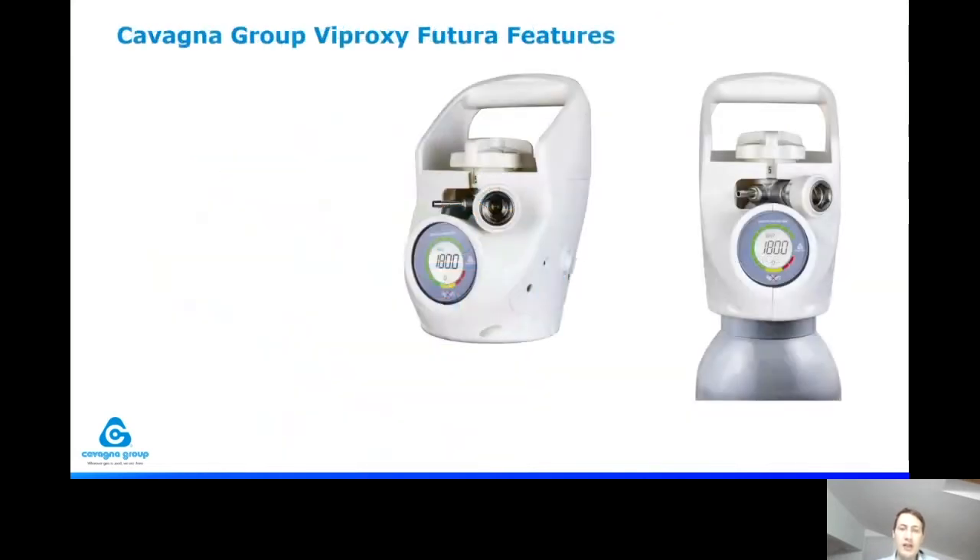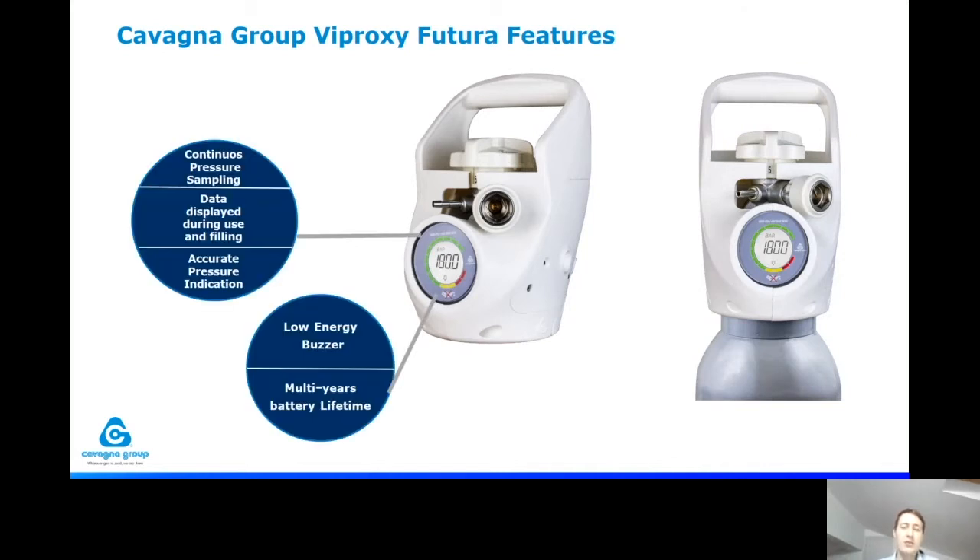The Viproxy Futura is the oxygen valve dedicated to the healthcare sector, for use in hospitals, ambulances, and home care. It has different features, including the ability to monitor and see from the display the pressure inside the oxygen cylinder continuously. When the valve is open, it also shows the quantity of gas and time left. Of course, there are visible and audible alarms, and a battery with multiple years of life.